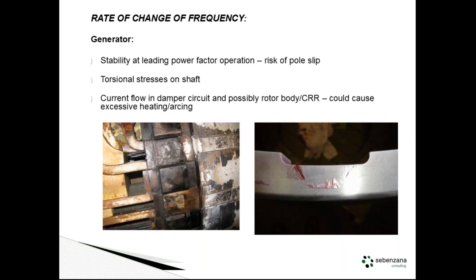A big turbine generator shaft — what are they, 40 to 50 meters on these big machines, totally end-to-end — is nice and stiff in one plane, but in terms of twisting resistance, not that good. So you're putting torsional stresses on by rapidly changing frequency, with potential to cause long-term fatigue damage. The other issue, of course, is on the generator: you've got a damper circuit designed to handle negative sequence currents and maintain surface currents in the rotor, and it's also there to keep the machine synchronized.